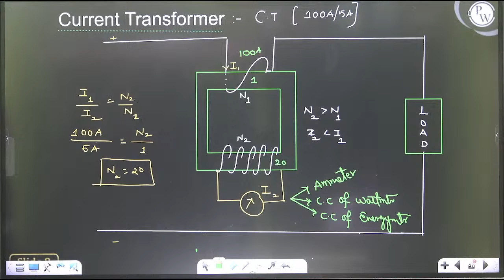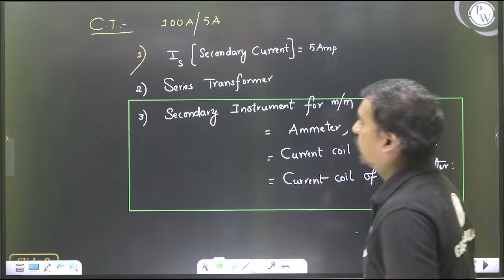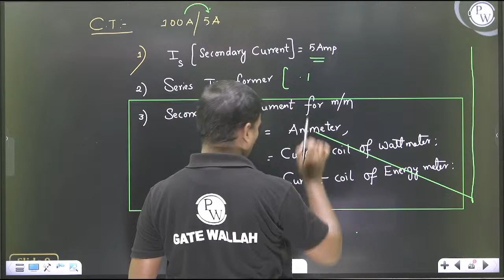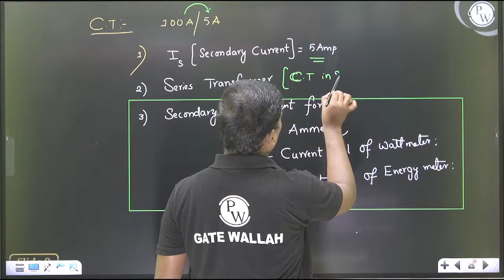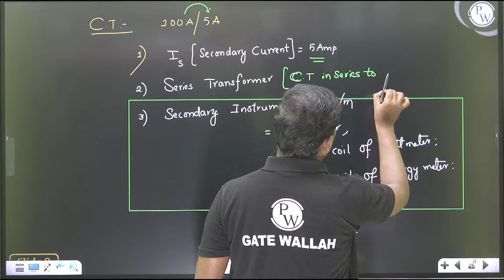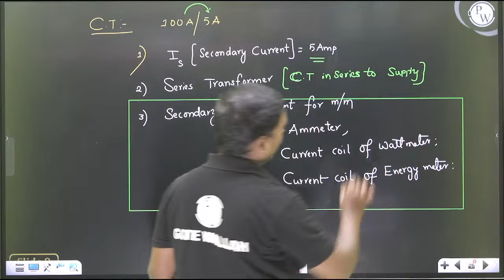Please make a note of these points. So if you see the features of the current transformer, the rating is majorly 100 amperes to 5 amperes, so the secondary current rating is 5 amperes. It is called a series transformer because the current transformer comes in series with the supply.